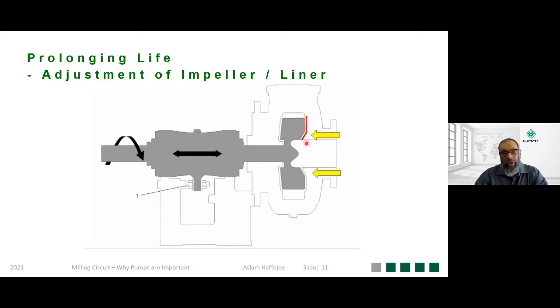Your liners will also wear evenly in doing that. The one big advantage of this scenario is that you can actually carry this out with the pump still in operation. But it needs very trained hands, skilled hands, because you've got to know what you're doing, and it's definitely a plus for having a multi-circuit pump in particular.